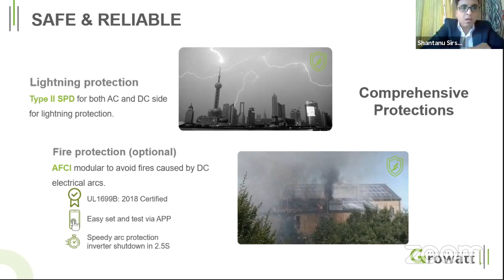And talking about maintenance, if you have the SPDs directly integrated in your power board, then if the SPD fails, it is required to replace the whole inverter, or you have to replace that particular inverter board. So what we are doing for the Growatt inverter is that we are providing a separate PCB for AC SPDs as well as for DC SPDs. So in any case, if there is any sort of failure in the SPD due to lightning or any other surge, then we only have to replace that particular SPD board and not the complete unit. So this helps in minimizing the after-sales support time.